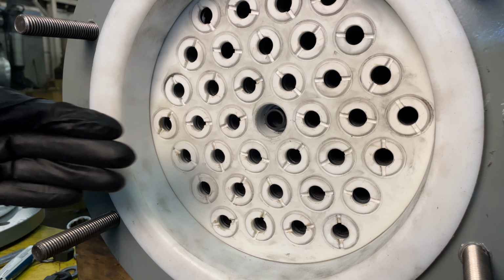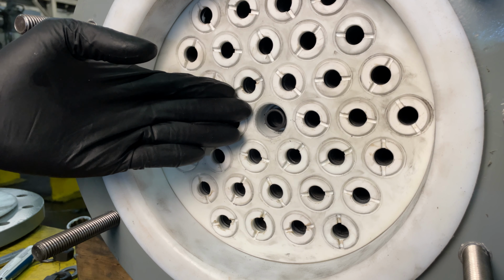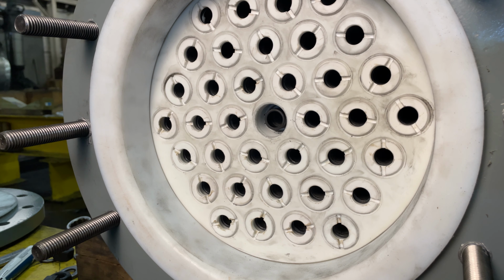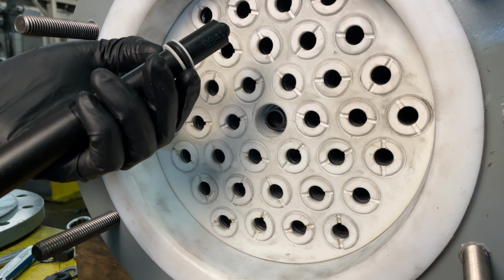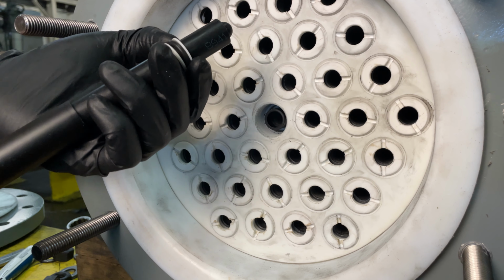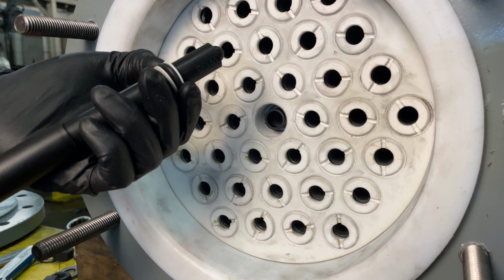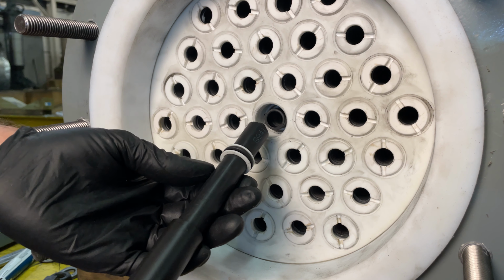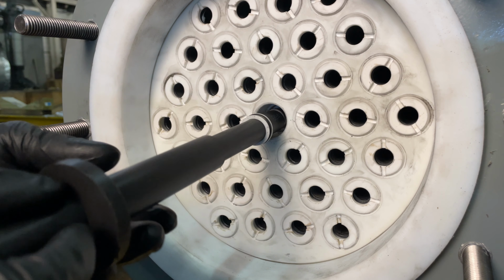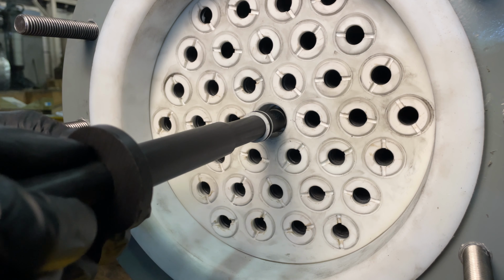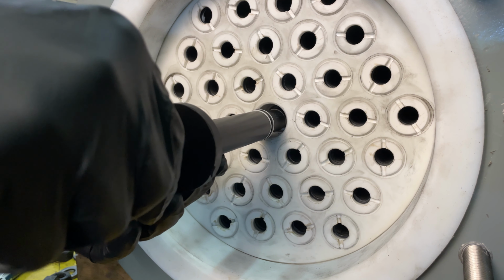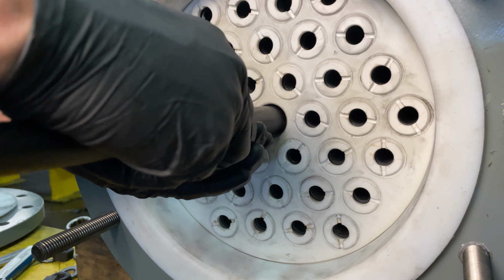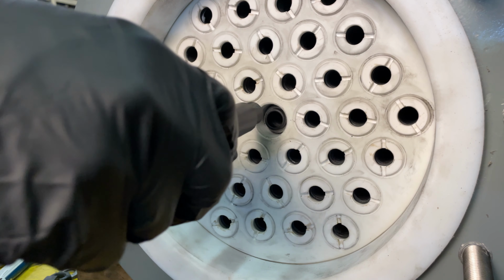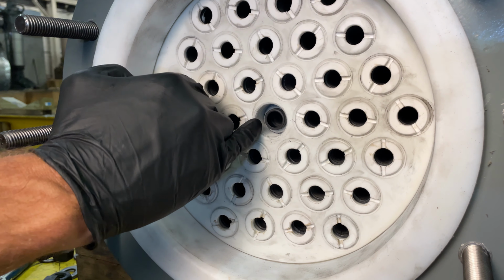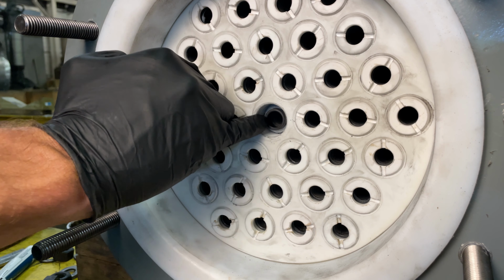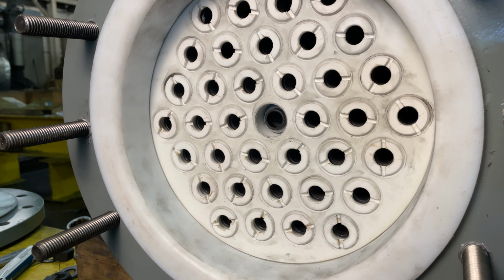On the opposite tube sheet, we don't have as much working room because the tube sits inside the tube nut pocket. But we'll begin by placing the backup ring, O-ring, and backup ring on the positioning tool just as we did on the other side. We'll locate the positioning tool on the tube inside the pocket and slide the positioning tool handle forward all the way. Now when I remove the positioning tool, I'm going to ensure that the secondary backup ring is still sitting around the tube and did not fall off into the tube nut pocket.